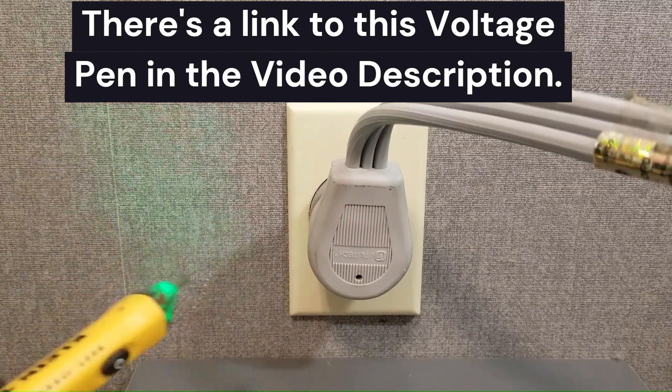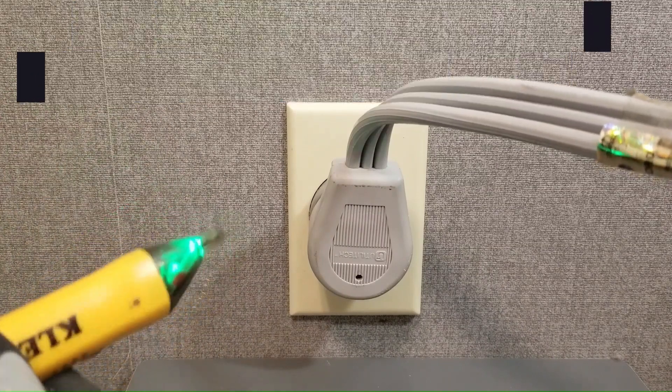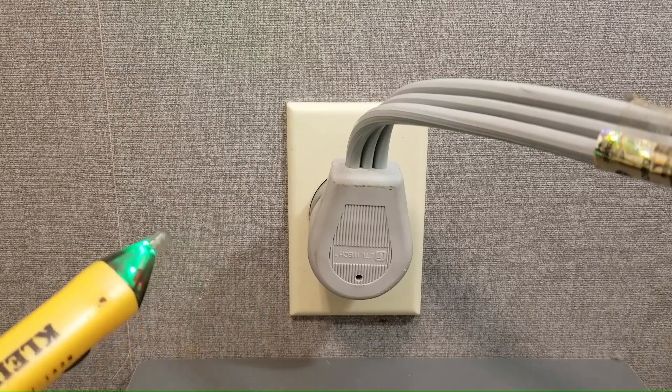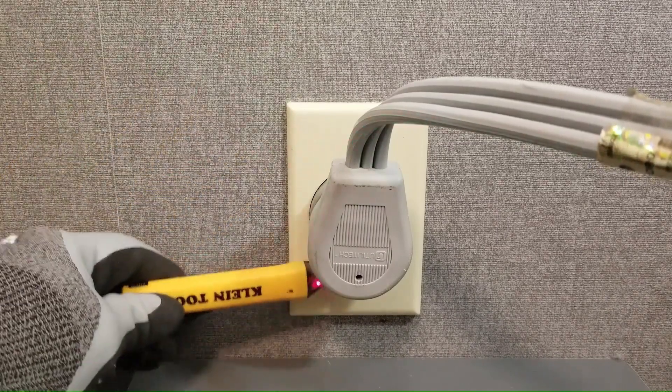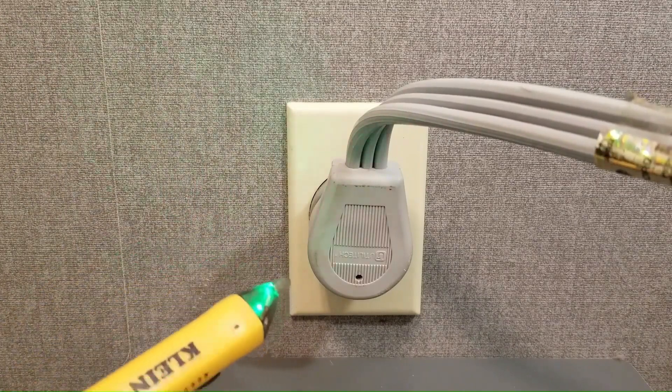It's not always definitive because sometimes the floating neutral doesn't pull up that high but in the vast majority of cases a floating neutral is going to pull up almost up to the potential of L1 or L2. So that neutral is signaling so that tells us we have a floating neutral.